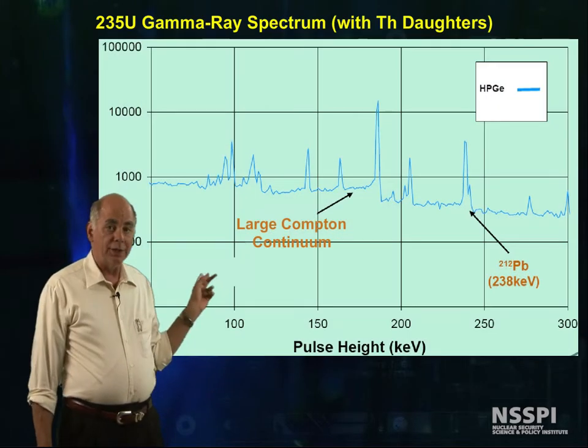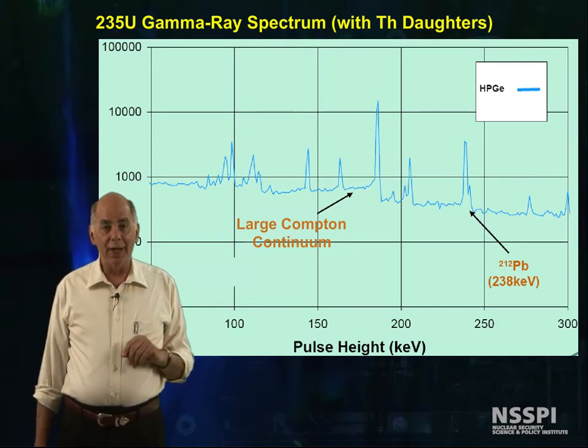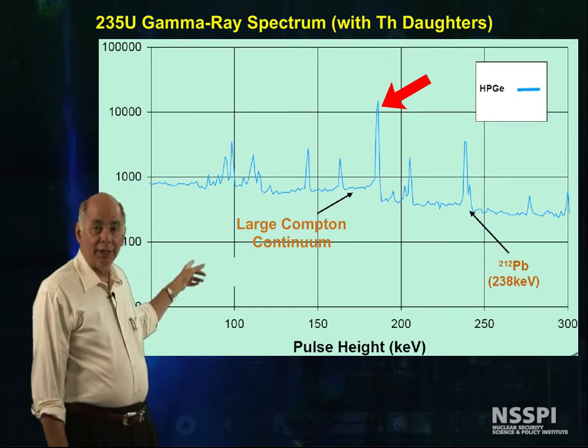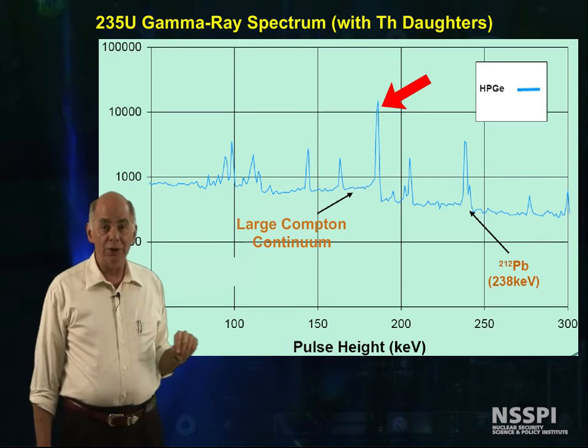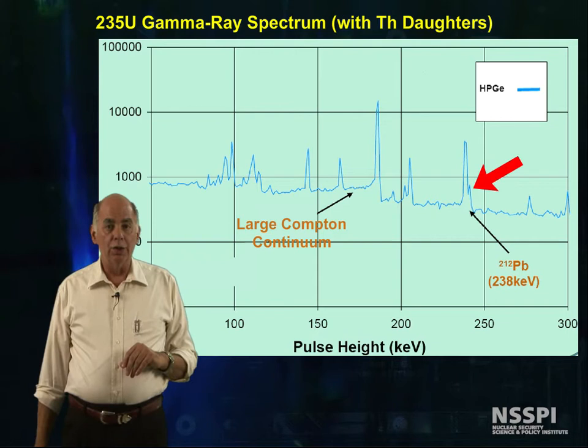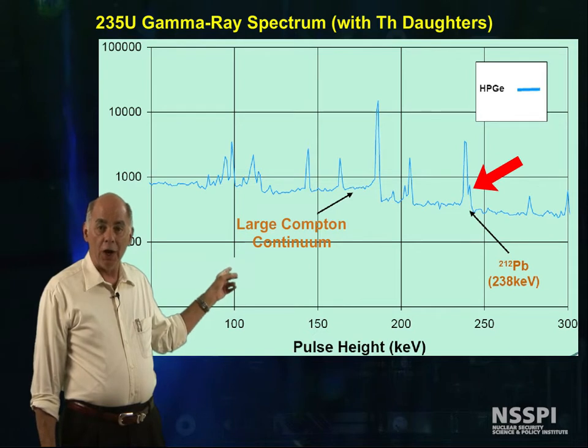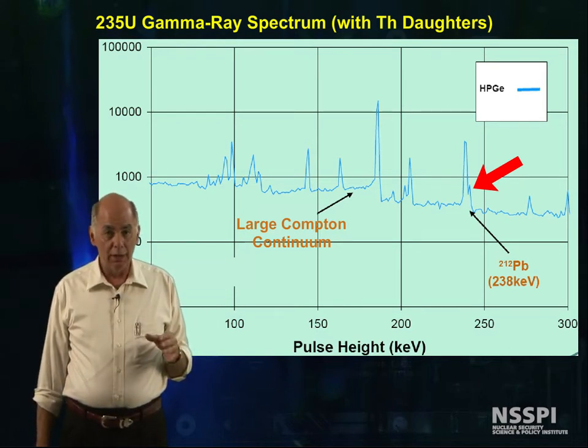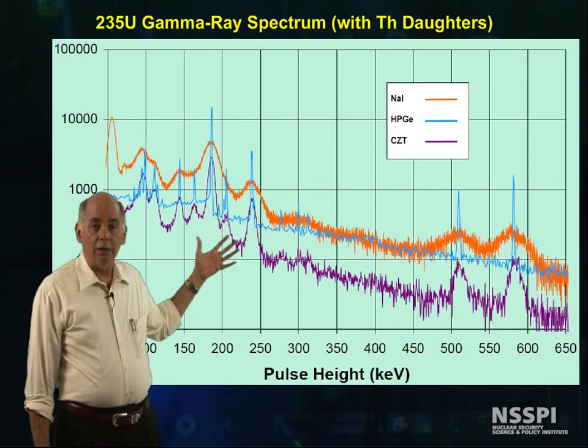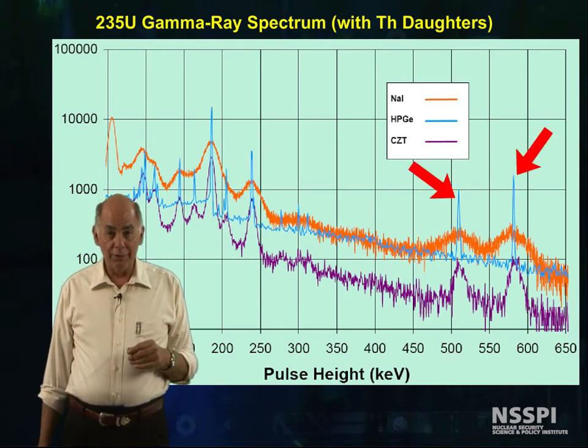Now let's look at a spectrum that is not quite so pretty, and see where this Compton-to-186-line ratio would lead us astray. If we look at our 186 line, we see that in this spectrum it sits on top of a large Compton continuum generated by higher-energy photons. The lead-212 gamma is a clue that something is not right — this is the daughter at the bottom of the thorium chain, not the U-235 chain or the U-238 chain. If we zoom out, we now see that there are peaks from the ingrowth daughters above 250 keV.